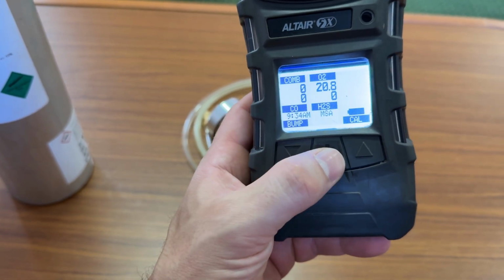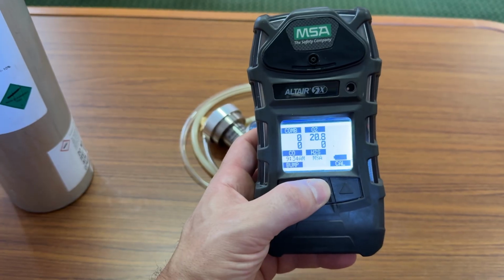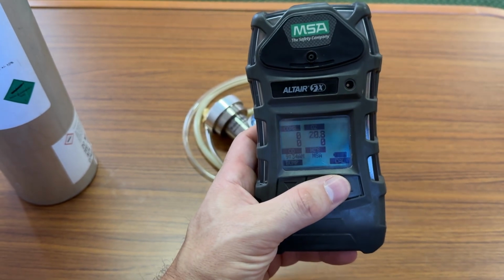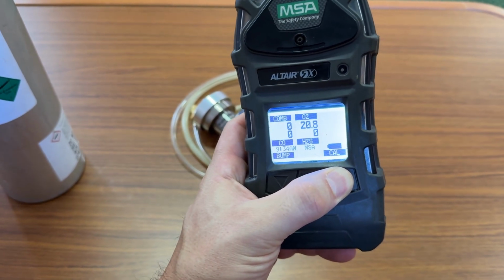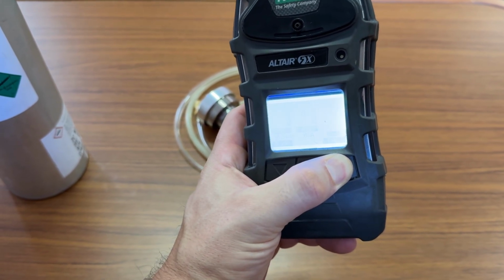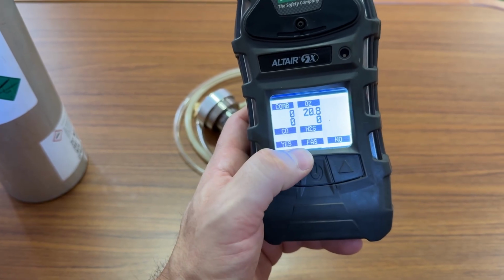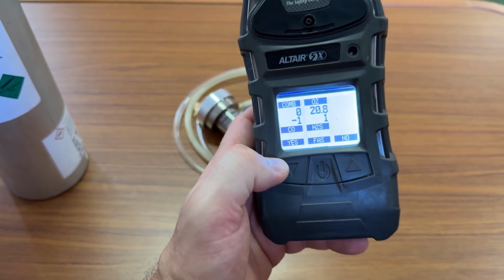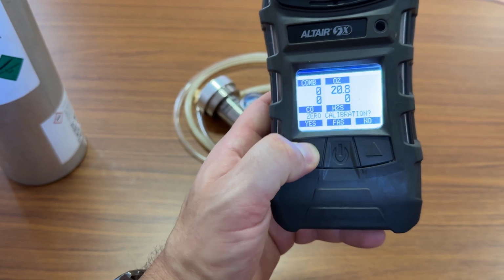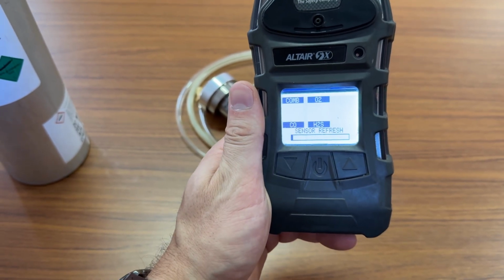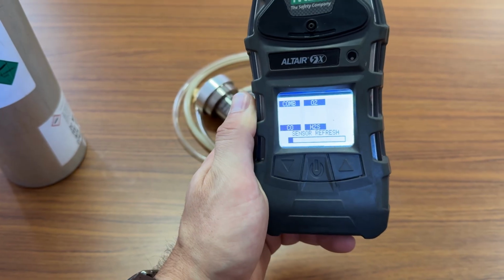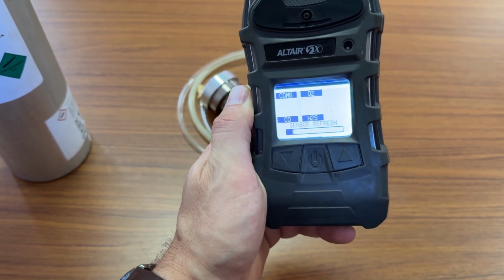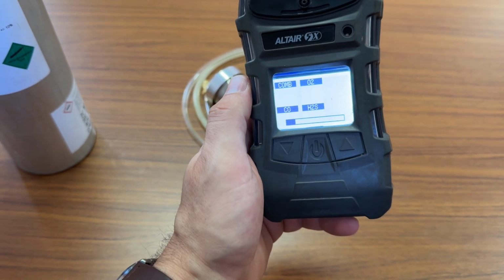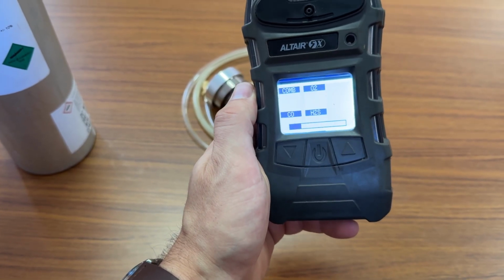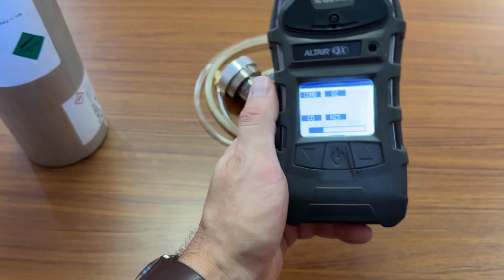Okay, before starting the calibration, we need to just hold on this right button and you will see zero calibration. We need to pass this zero calibration test. Press yes. It's checking and refreshing the sensors. Before any calibration we are making this zero calibration test. It will take some time.